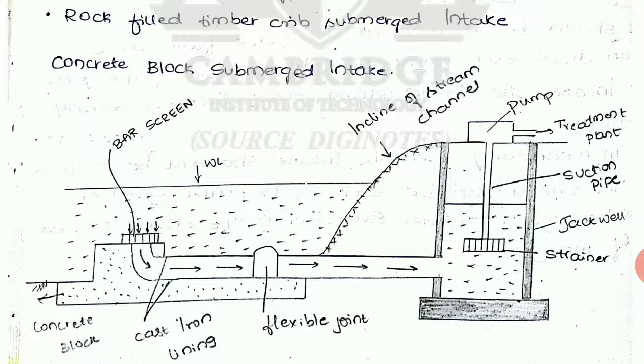And below the sand, sometimes concrete blocks are also used to retain the pipe, and the pipes used are cast iron pipes. And here you can see the flexible joint, because of the water movement, there will be a little movement of the pipe here and there, like the vibration, that can be withstood. That's why the flexible joint is provided for the pipes.